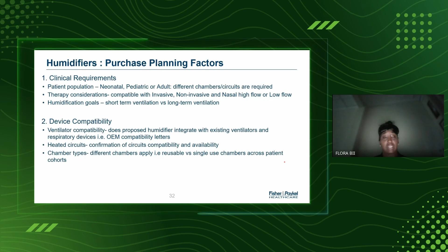As well as that, one that is common and we forget a lot, this one is fairly overlooked, is just the plug type and voltage compatibilities. Now, many centers, for example, in many of our East African countries where these MR850s are used, we use 220 to 240 volts. Others would be using 110 volts. Now, there are situations where there'll be an increase in cost because of needing to purchase step up or step down devices, just because voltage compatibility was not put in consideration earlier. And also just checking other things around the environment, around water supply: where are you going to source your sterile or distilled water? Is it available? To prevent the crystallization of humidification chambers. And also just checking for other basic things that as biomeds, we also look at.